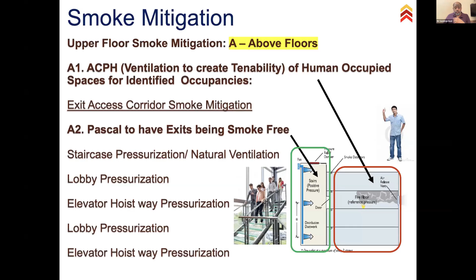The exit is the red-green box where you create pressurization to eliminate smoke entering the spaces used for exits. Within the Pascals of pressurization, you have staircase pressurization, natural ventilation, and lobby pressurization - hoistway pressurization got repeated twice, so the first three lines are correct. This is all about pressurization, and the goal is to create those spaces so people leaving the building are not exposed to the hazard of smoke.